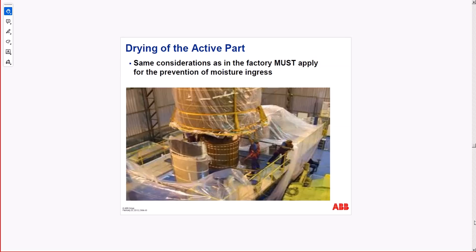Drying the active part, we apply drying a lot of times. We have moisture, and we apply drying by low frequency. This is a process that is applied for motors that were not properly maintained on site and got ingress. We apply heaters. Anything like switchgear and even generators needs to have a certain maximum percentage of moisture. If it's more, they don't pass, like motors or transformers, they don't pass the Baker test. They have a very low polarization index number, which means a lot of moisture in the windings, in the actual insulation, and that is not acceptable. So to put it in service, you need to pass all those Baker tests, dielectric test, PI test, tangent delta, and so on.